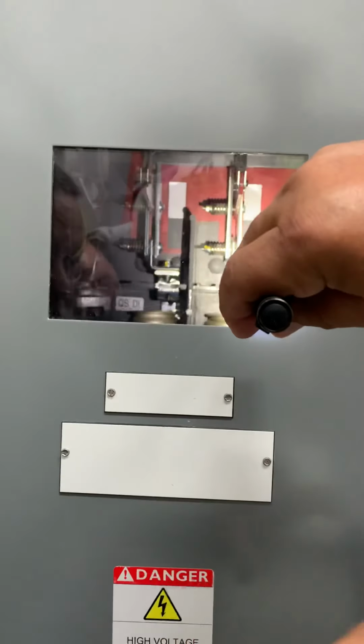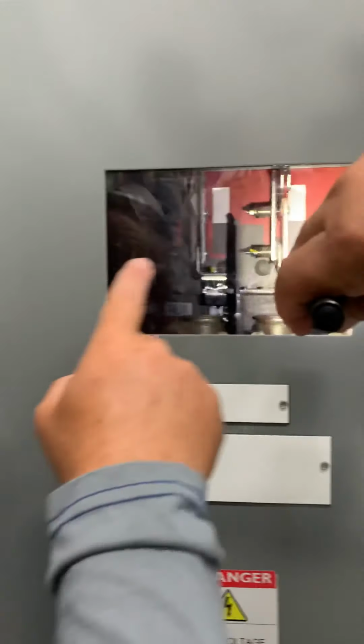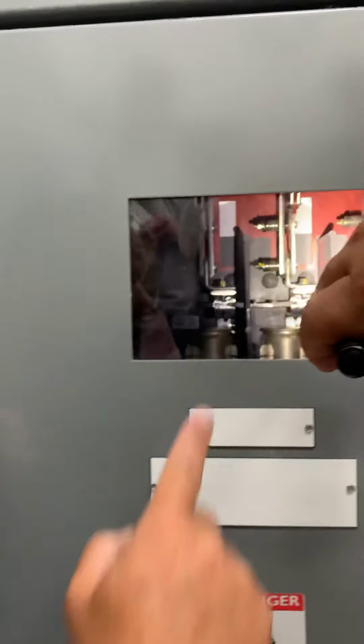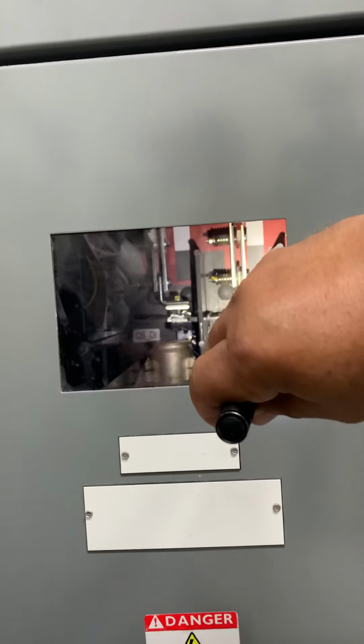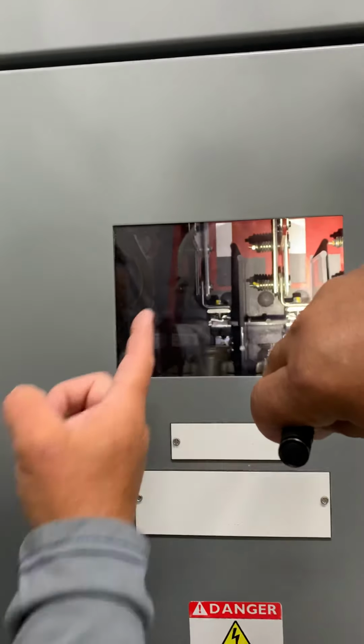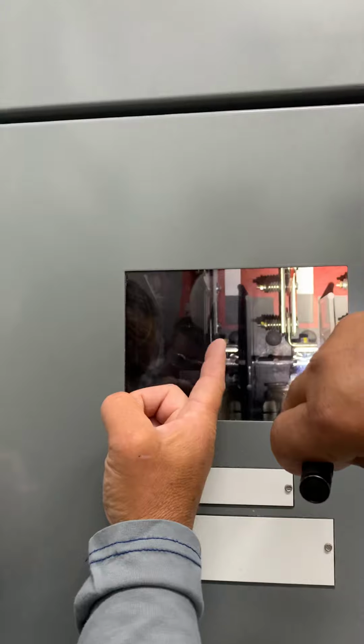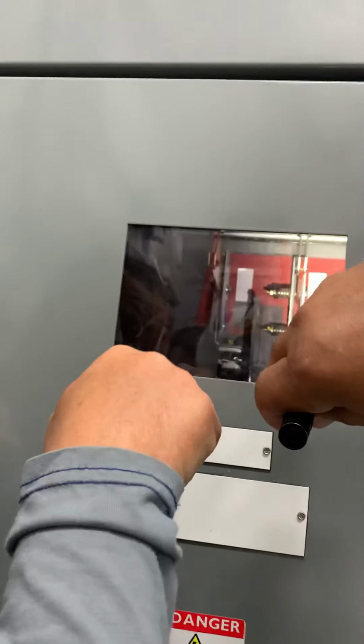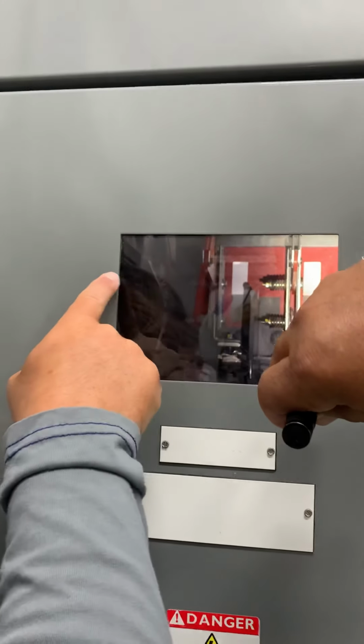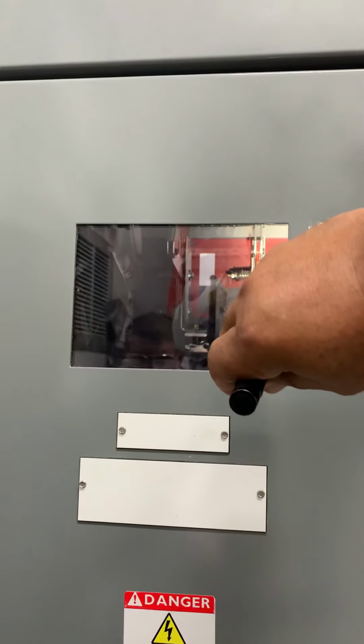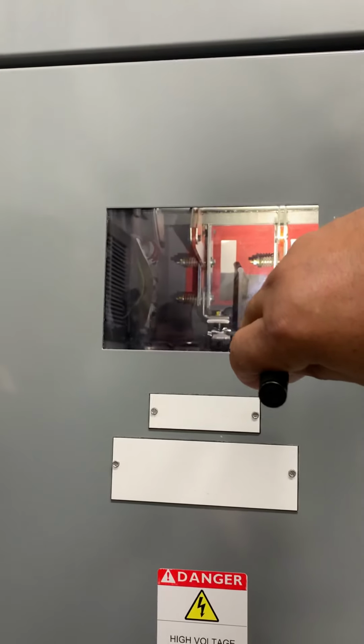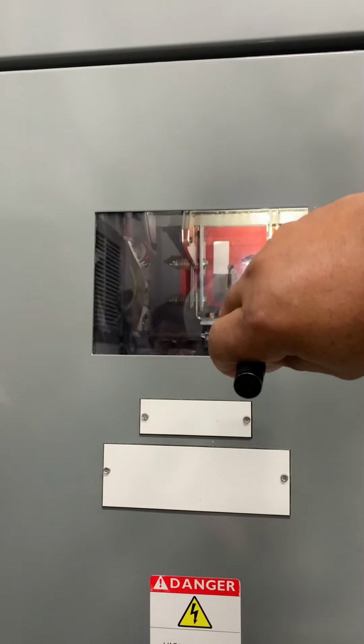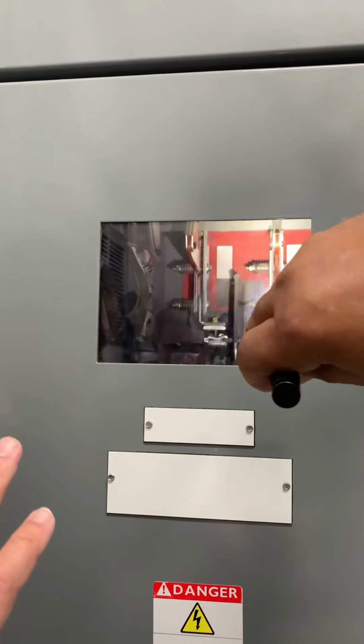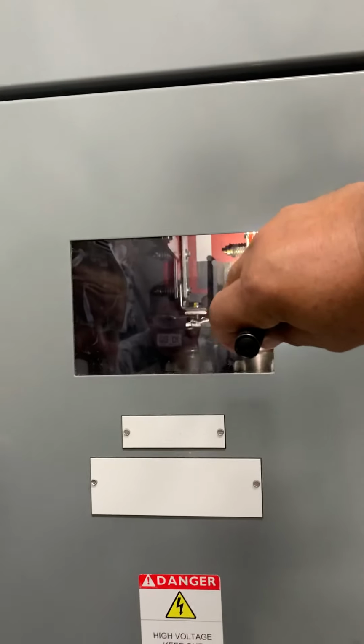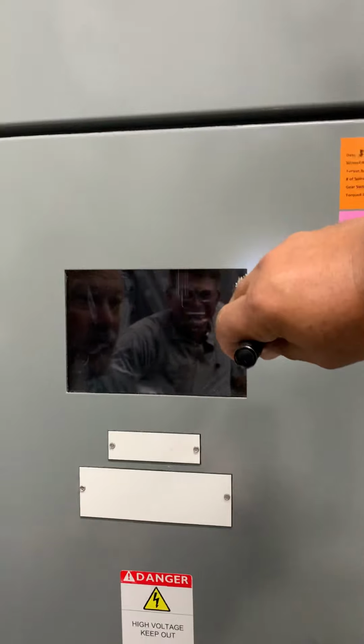If you're ever opening this, you want to make sure those white shutters are showing, and that lets you know that it's closed off from the medium voltage. And those blades, or the shears that come down, you want to make sure they're up against that grounding bus. That's a grounding bus up there to help pull any potential off of it. You still hot stick everything before you get in, but that won't be doing any of that. So whenever we turn that on, let me get these keys.